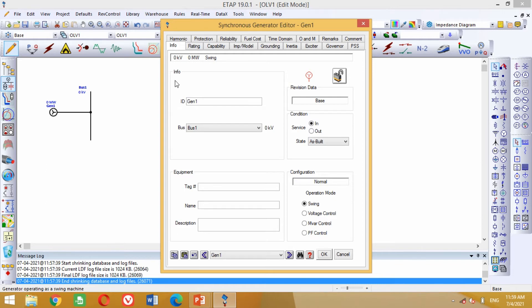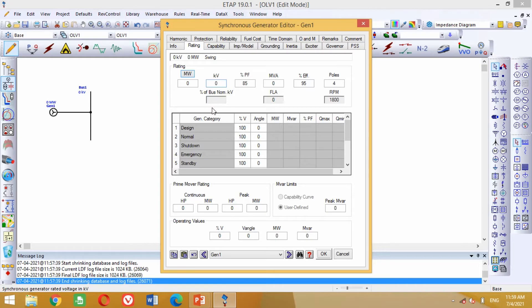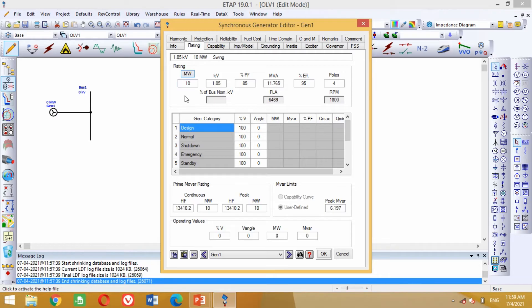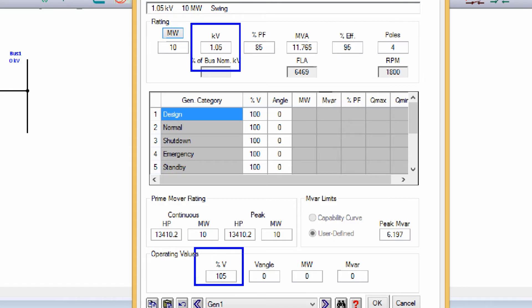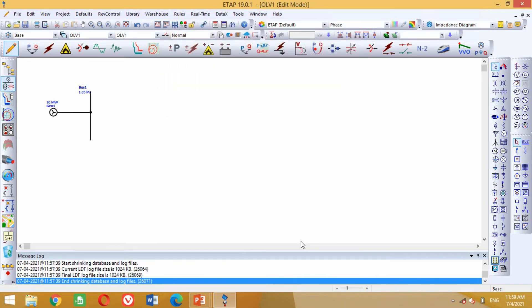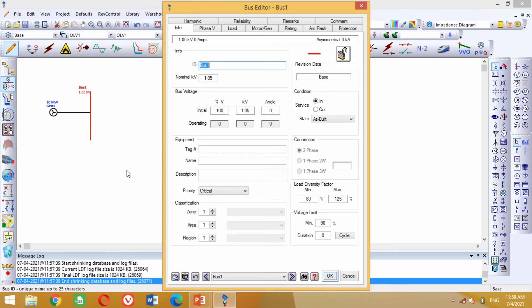Now click on the rating icon to insert the other values. As we know that the actual voltage as well as the slack bus power is not given for this example, therefore you can choose any random values. In this case, I am choosing 1.05 kV as the voltage value and 10 MW as the slack bus initial power. You can notice that here it asks about the voltage in percentage, so write here 105% because 1.05 per unit slack bus voltage equals 105% in percentage. Now double click on this bus to insert its data. As bus 1 is connected with the generator, the data is directly added here — this is the advantage of ETAP software. Therefore, no need to put any value here, just press OK.